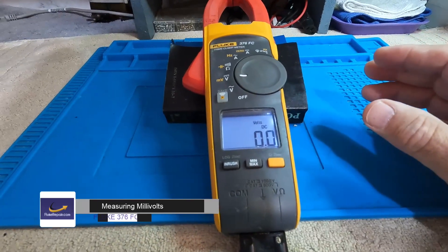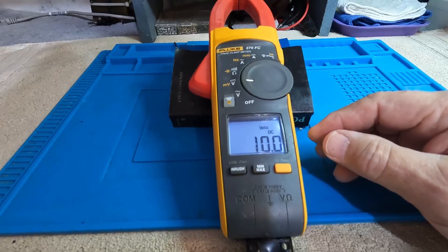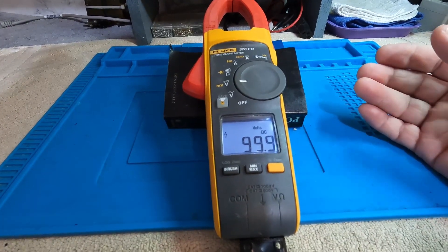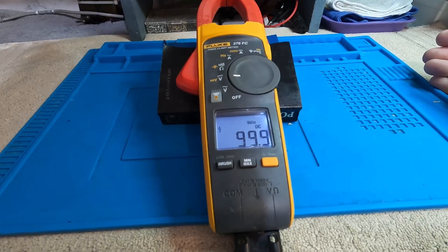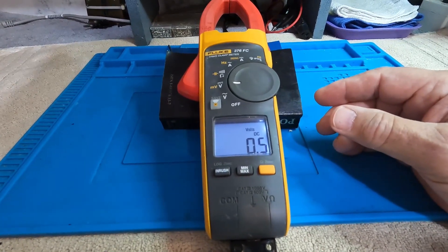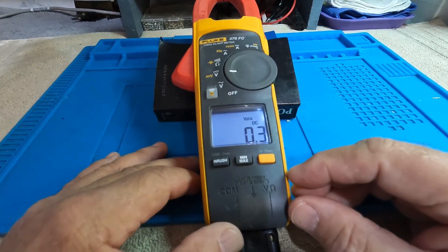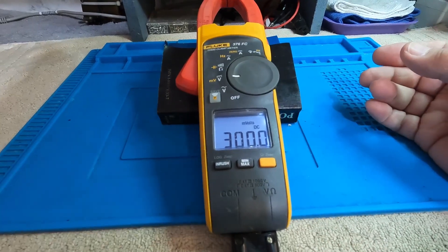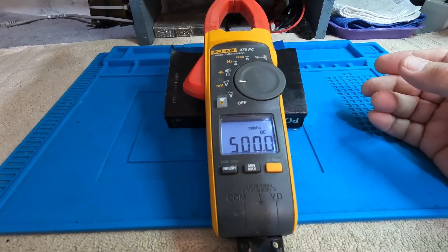On the DC voltage side, we'll start with 1 volt DC, then 10 volts DC, then 100 volts DC. This is an auto-ranging meter, so it selects the range automatically as you apply voltage — you don't need to do anything. To access the millivolt range, bring the input down to, say, 300 millivolts and press the yellow button — you'll see the yellow 'mV' indicator. It will switch to the millivolt scale and read 300 or 500 millivolts accurately.